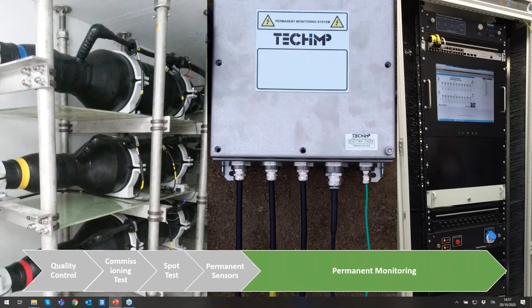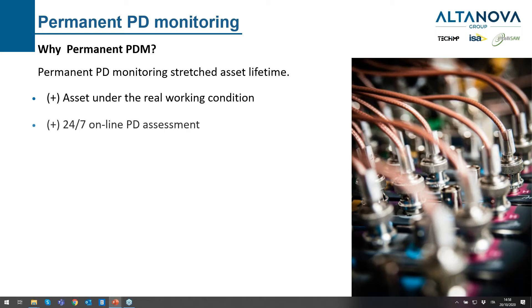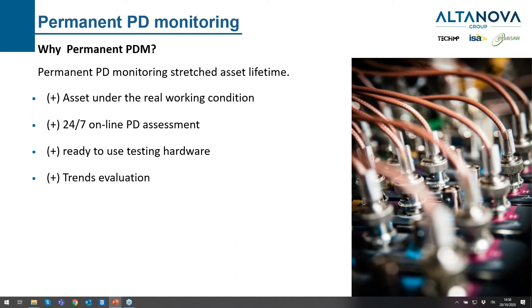The highest solution we can provide the customer is permanent monitoring. The asset works in real working conditions all the time. We have 24/7 online PD assessment. We also have testing hardware ready to use if we want to perform a manual spot measurement — for example, to investigate an alarm further; we just need to connect a laptop to the instrument. We can also have very good trend evaluation.